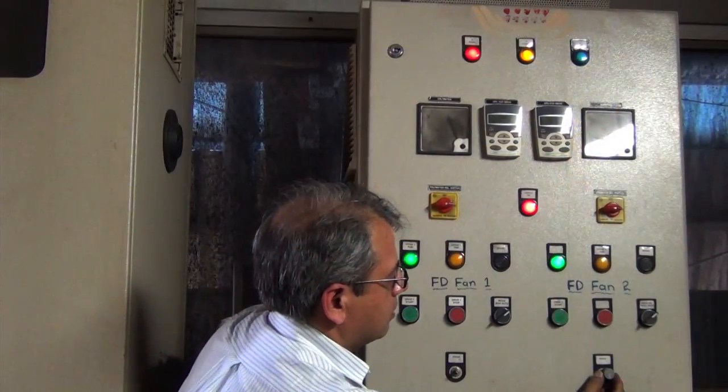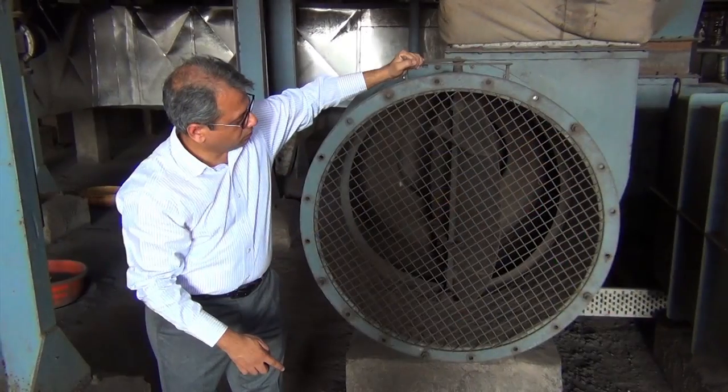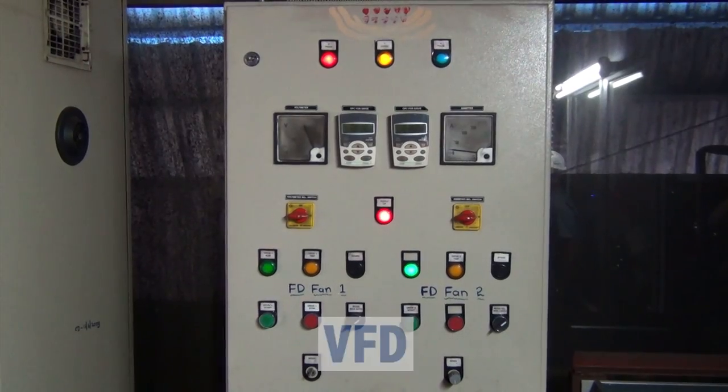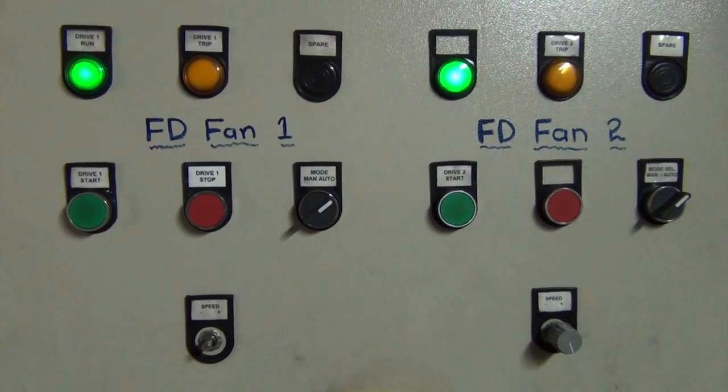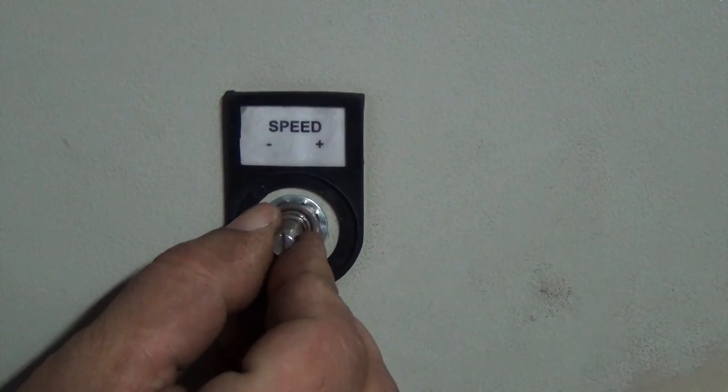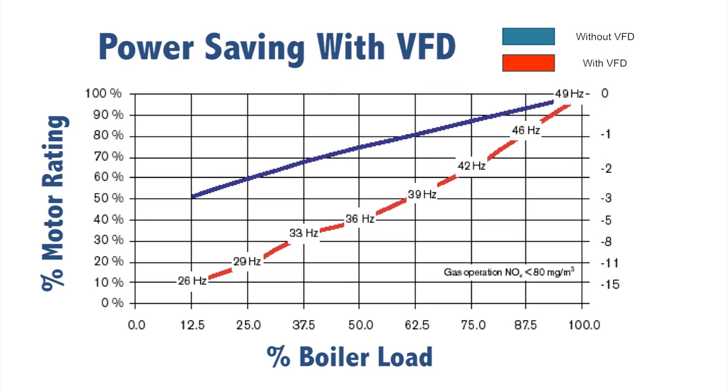This excess air can be controlled by either adjusting the speed of the FD fan or by doing the adjustment in the damper settings. Both methods are equally good and equally well accepted. The speed of the FD fan can be reduced by two methods: one is by using a potentiometer and one is by using a variable frequency drive. Variable frequency drives, or variable speed drives, are now increasingly becoming popular as a tool to alter the FD fan speed.